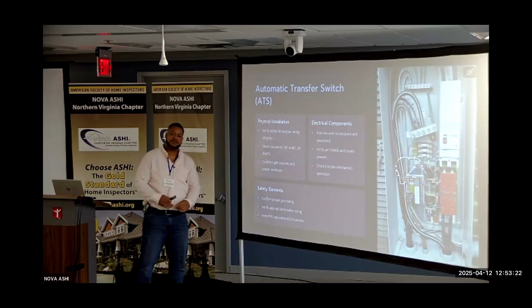So looking inside of this, as I mentioned, the grounding is very important. So in your houses right now, when the electrical service comes in, usually your main disconnect is in the house inside of your panel. Unless your panel is further than, let's say, 5 foot from your meter, then you have a disconnect outside. So this ATS now becomes the service disconnect. So now that means your inside panel is going to become your sub panel. So that means that you need to take a neutral from here into your electrical panel.